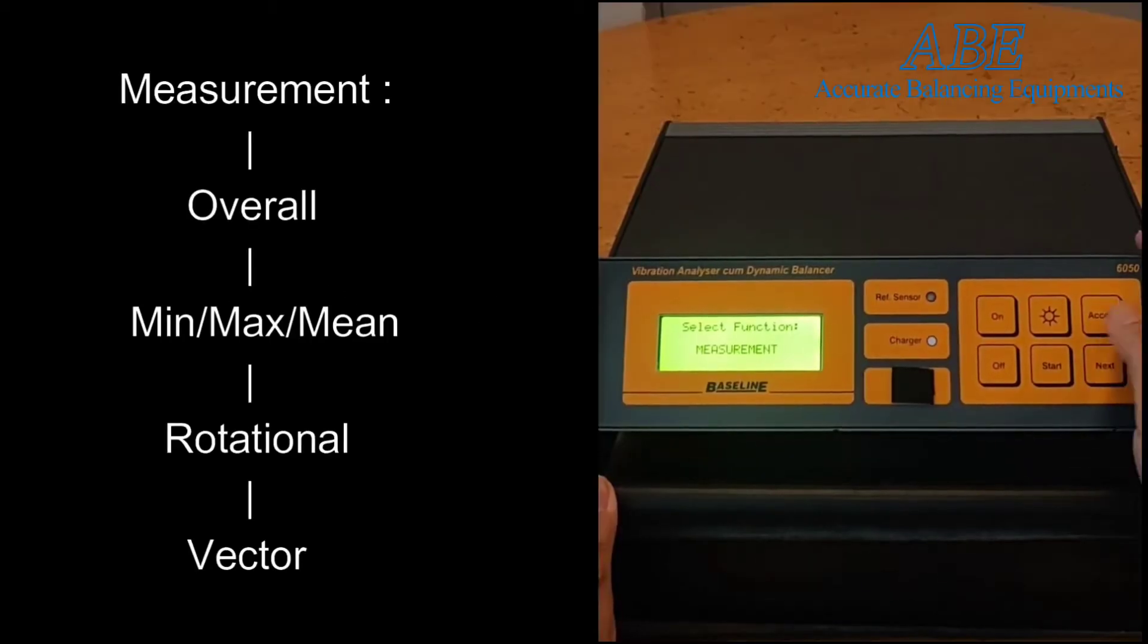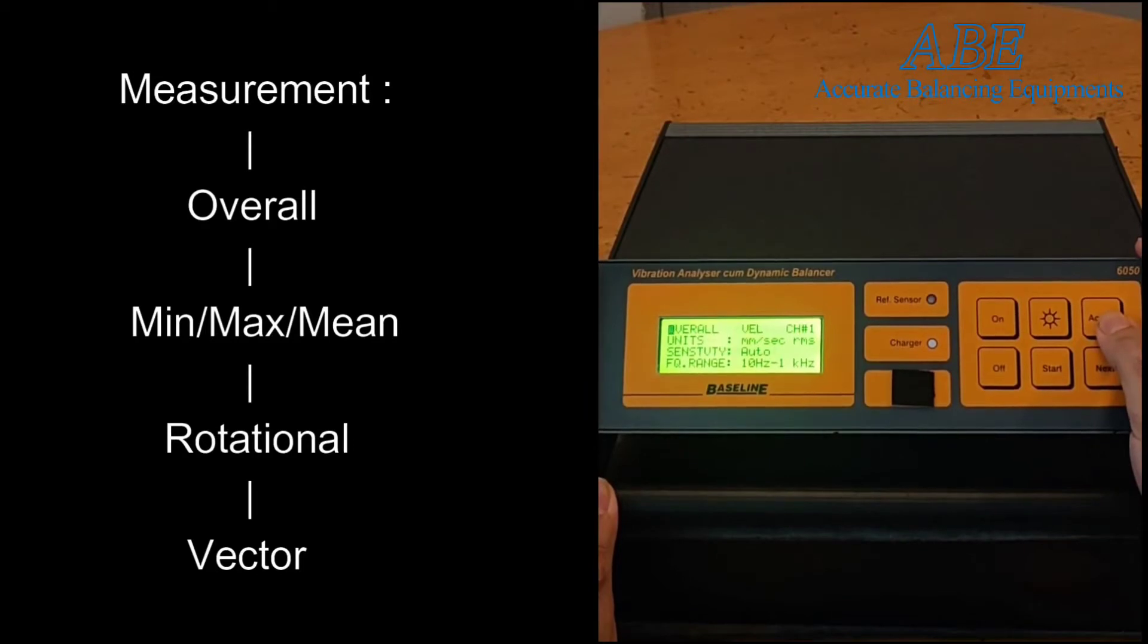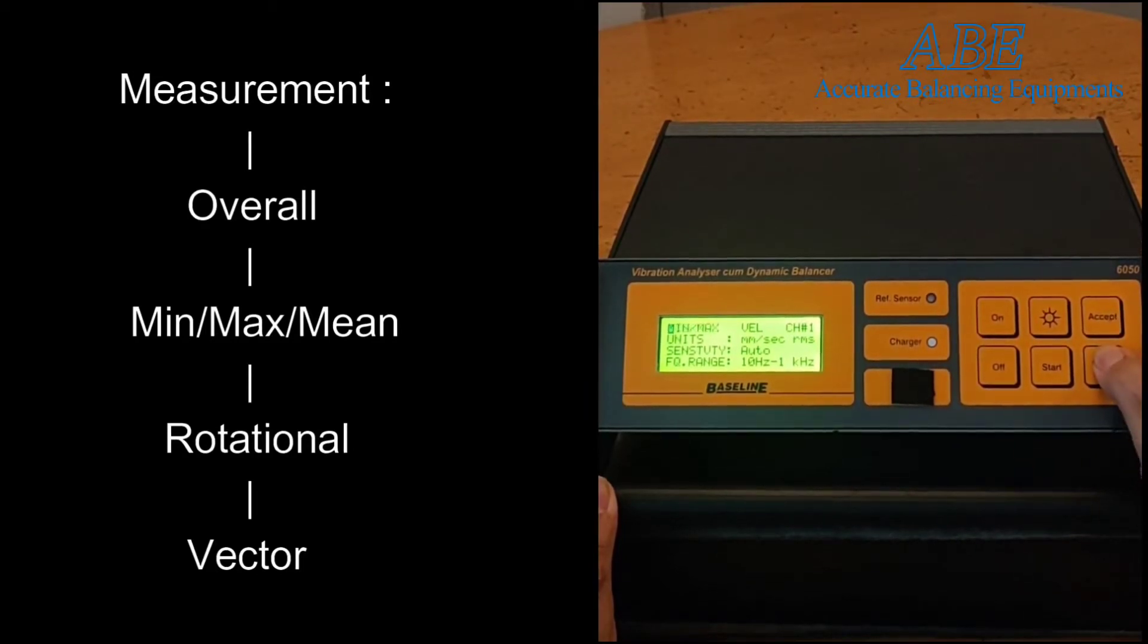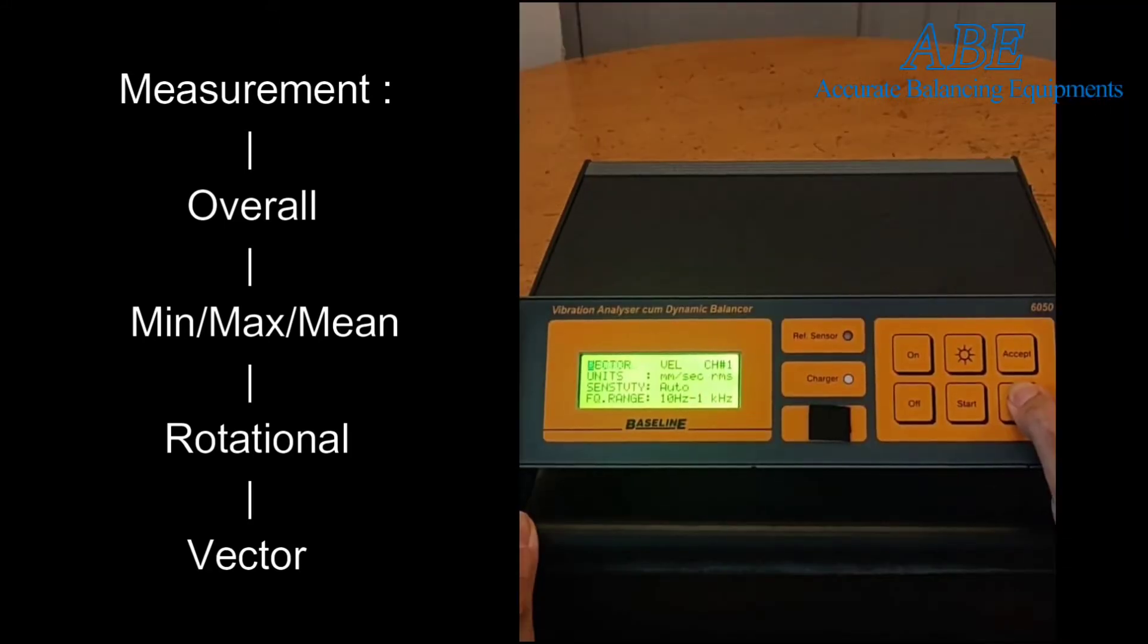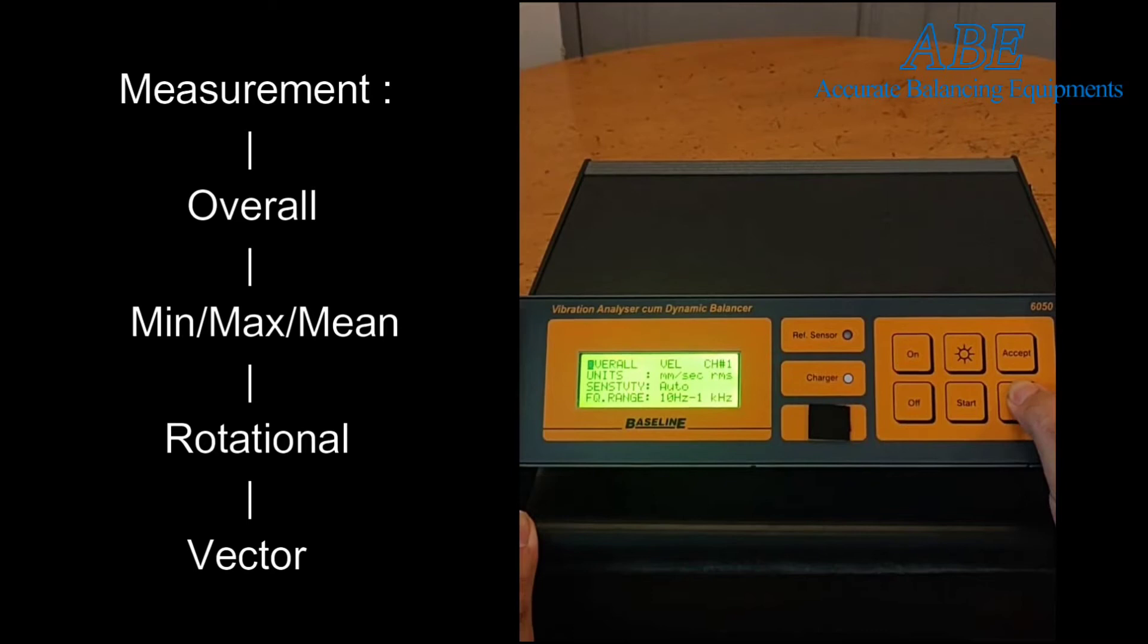Accept measurement and you get the following options: Overall measures the vibration of all frequencies together. Press next for min/max, which indicates the minimum, maximum, and mean of 20 successive readings. Press next for rotational, which indicates the rotational elements of vibration.